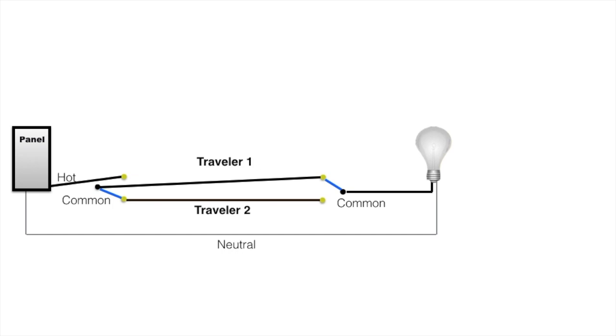What's going to happen now when I turn that breaker on? Well, if you guessed nothing happens, you are correct because all I did was I energized a traveler terminal on the switch which isn't going anywhere. You roll over here and you operate the switch on the left. And what do you know? The light went on. So you think you're doing good. So you run down to the other end and you operate that switch. And sure enough, the light goes off just like it's supposed to. But we'll check again. We'll run down to the first switch, operate that. The light should go on. And, uh-oh, the light doesn't go on. We're back to what we started with. And now you know you've got a problem.